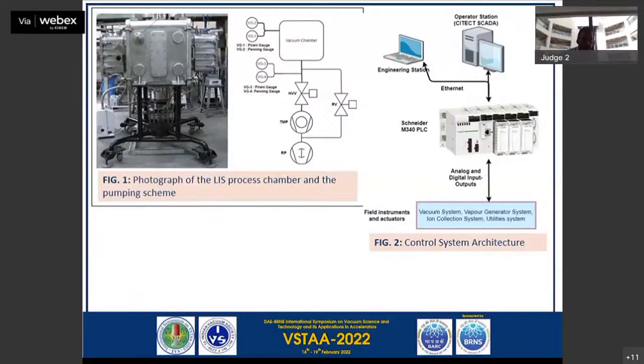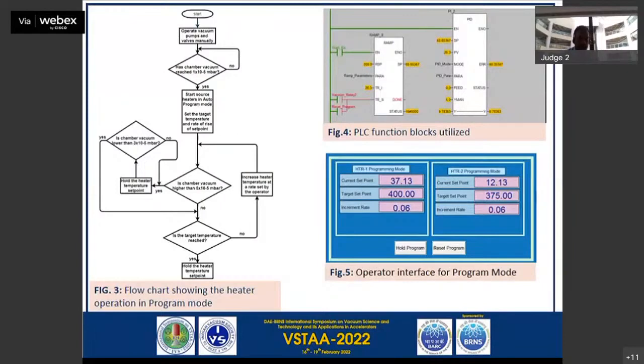On the left is the flow chart showing the heater operation in program mode. Basically we keep monitoring the vacuum, and if the vacuum goes bad, we hold the ramping of the temperature; otherwise we continue the ramping. This has helped us in expediting the process.